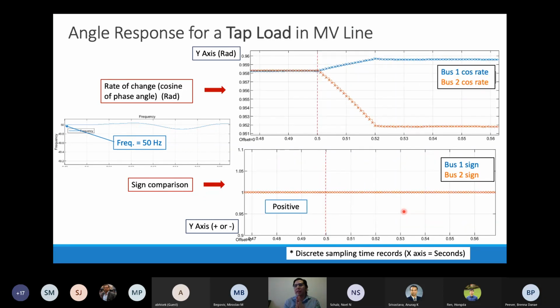Here I'm testing, in contrast to that one, a tap load, which happens again at the same time, 0.5 seconds. I'm trying to see how the relays detect this tap load, which is different from the fault. We can see on the bus, in the blue line, how it's detecting from end number 1, and in the orange one we have end number 2. When the tap load enters, since neither signal detects a change in current flow, we can see that the cosine of the angle is still positive. So our relays won't trigger in this scenario.